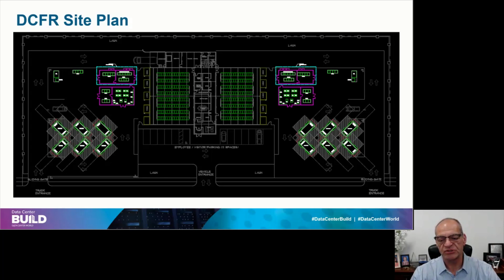But I do want to point out a couple things. First of all, the natural gas utility is running through the linear generators, and you'll note it's running not just the critical load through the A side of the static switches, but it's also running through transfer switches, the building loads and all the mechanical loads. And the electric utility and its non-redundant UPS is actually the B side, and it's on standby. And we'll actually utilize this through the linear generators. And by the way, it's not hard and fast. The UPS could be half on and half on through the linear generators as well. If you wanted to get rid of the static switches, you could do that. But again, I think the approach here is very good.